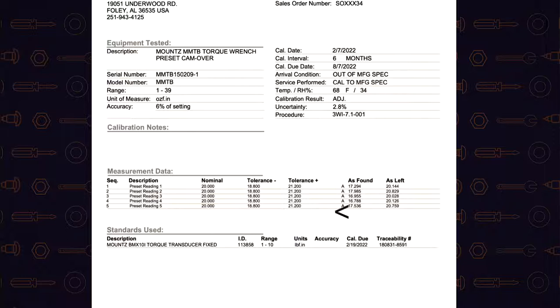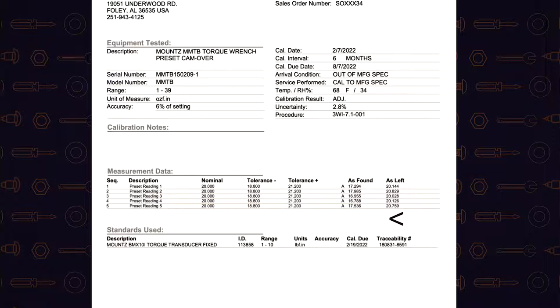We have a tolerance of 18 to 21 for our actual accuracy. As found, all of the readings were a little bit on the low side. The calibration adjustments were made and then the readings show what the tool left as. This is a good example of a tool that came into our lab that was out of spec for calibration — not out terribly, but it is out of spec.